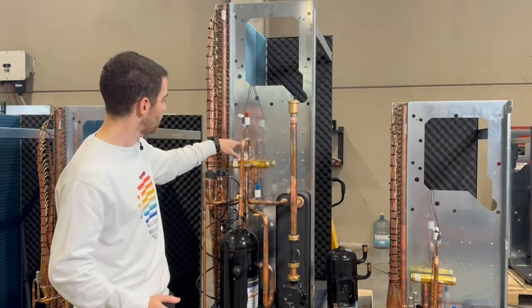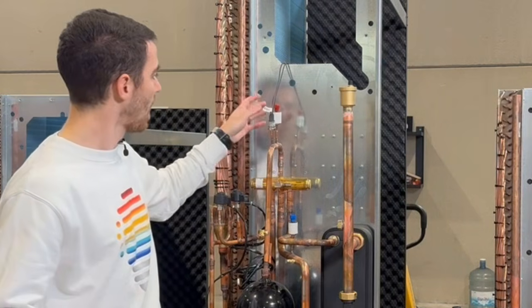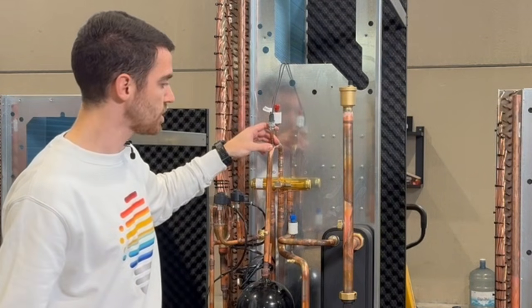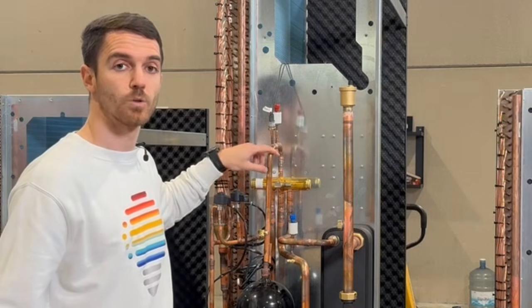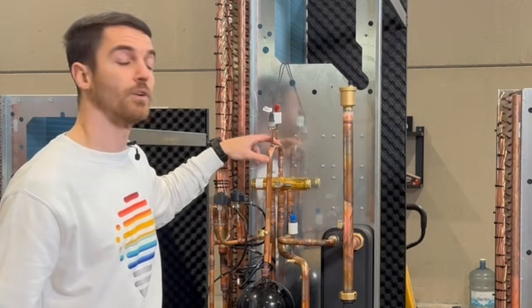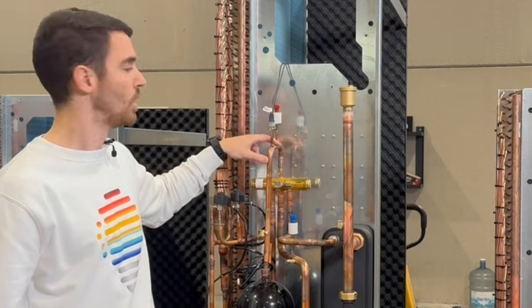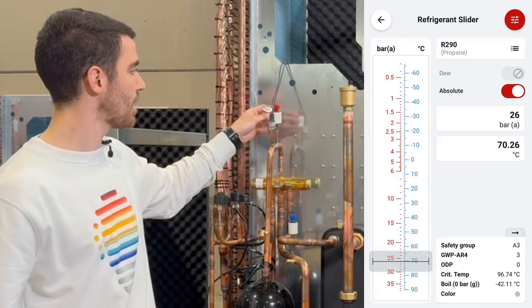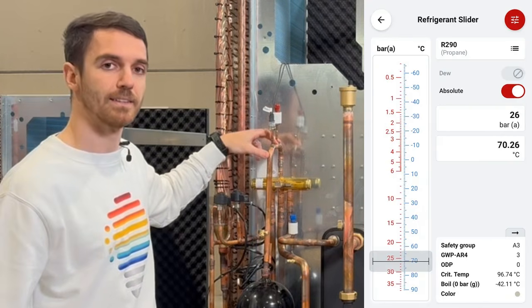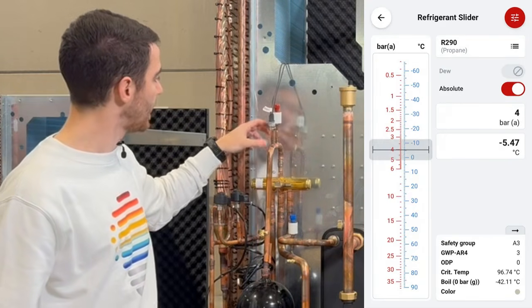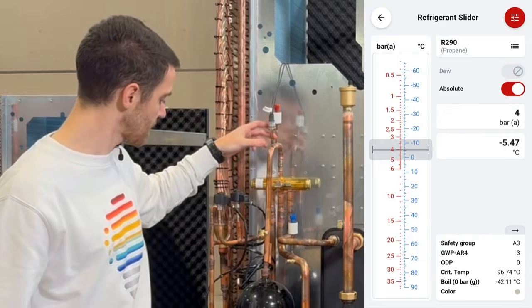What else we have here? 4-way valve, high pressure, low pressure sensor. Important to mention that this is R290 and we have different pressures than in R32. So around 26 bar is high pressure sensor. It's approximately 70 degrees. And 4 bar is low pressure sensor.